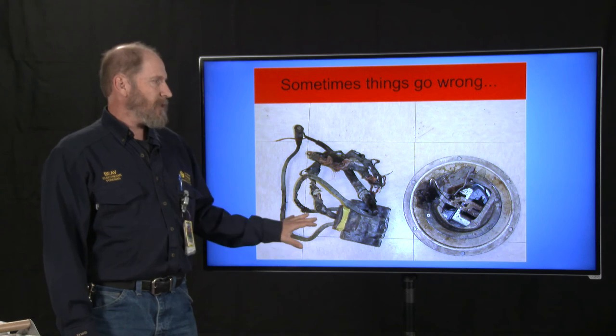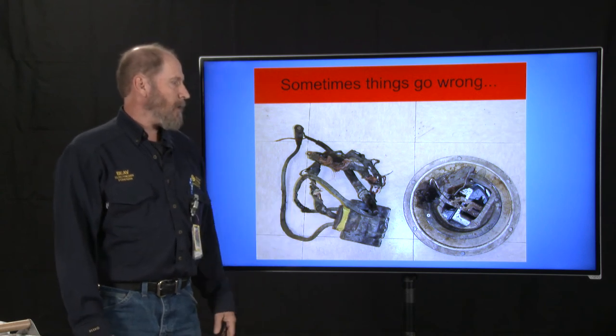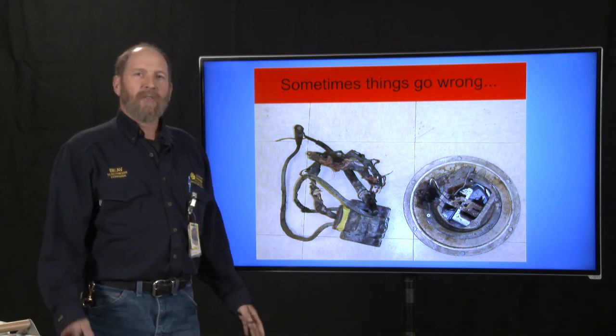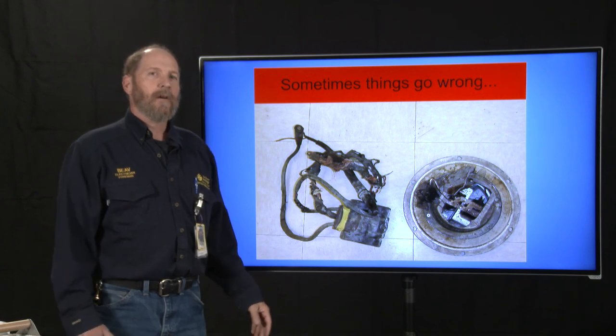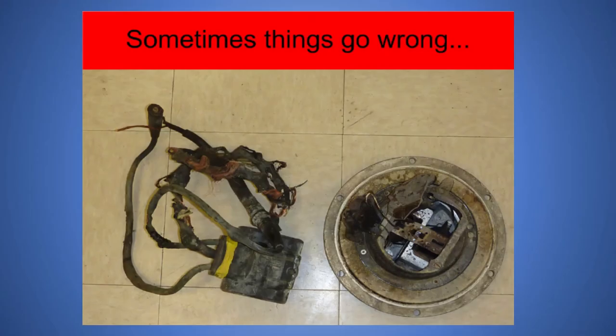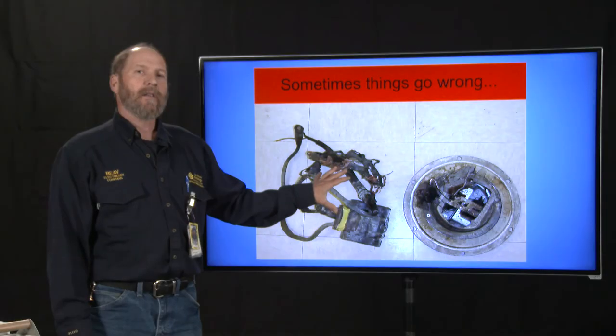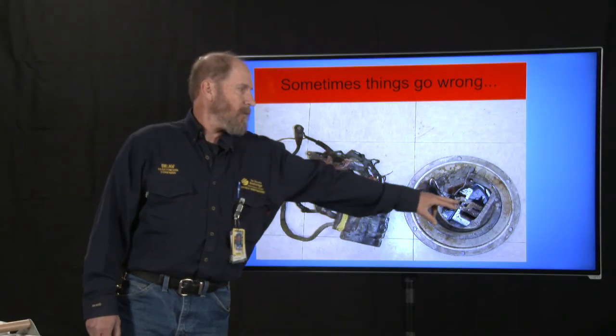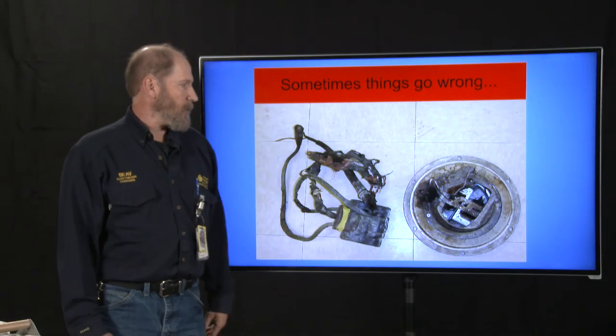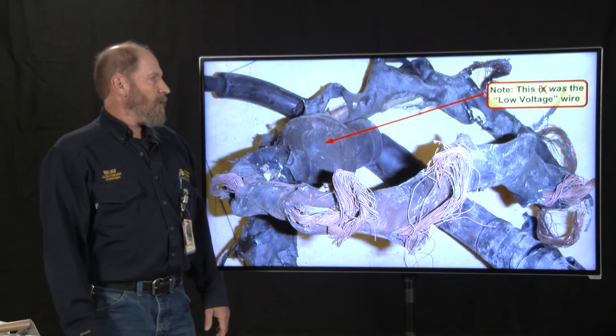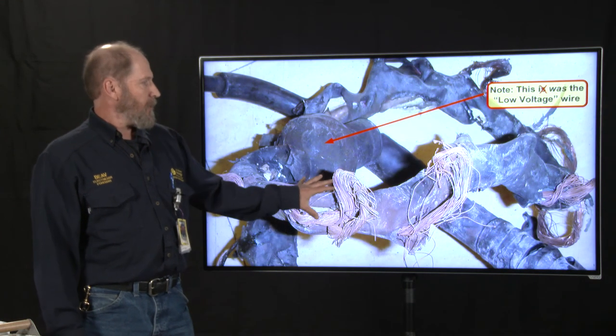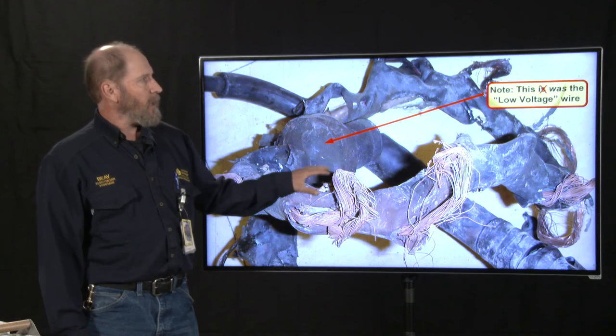This particular fixture happened out on the airfield here. We were called, there was a geyser shooting up about 20 feet in the air. Circuit was working just fine. We went out there, opened it up, shut it down, of course, and then opened it up, and this is what we found. It had been so hot inside of there that it actually melted the aluminum off of the back of the fixture.